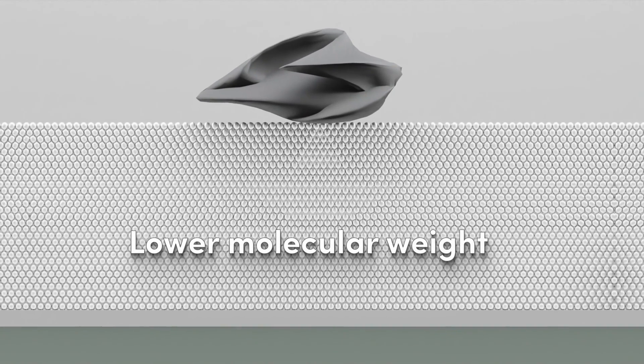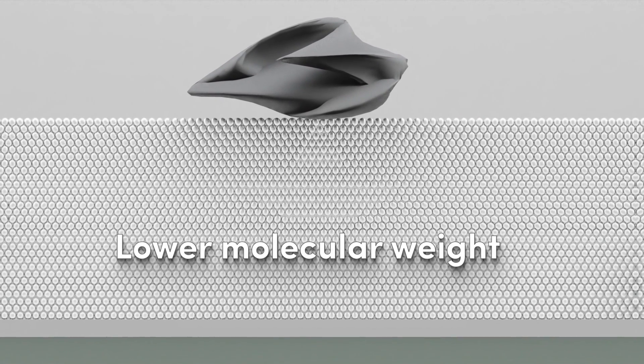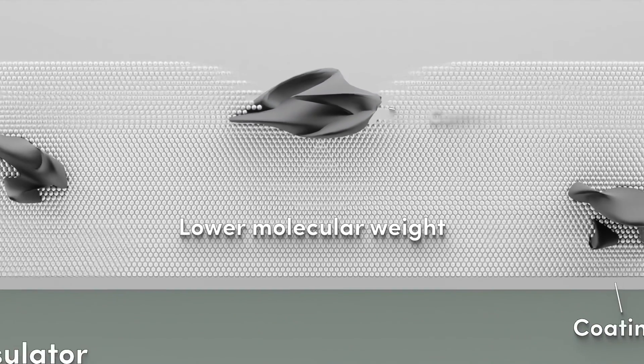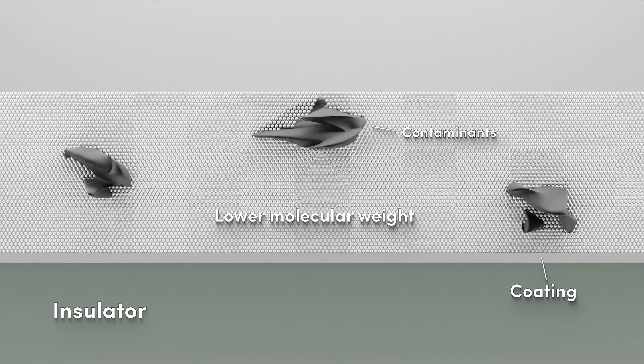How? The lower molecular weight fluid available in the bulk of the coating will be diffused to the surface of the coating, encapsulating the pollutant's particles and rendering the surface of the insulator into a hydrophobic one. Its non-wetting characteristics will surround all particles that come close with a monolayer fluid and avoid these to combine with water.